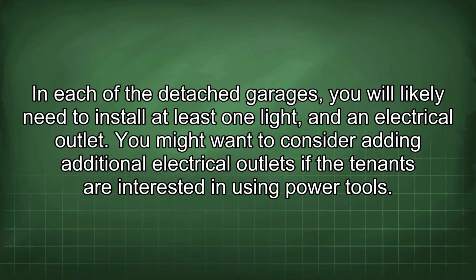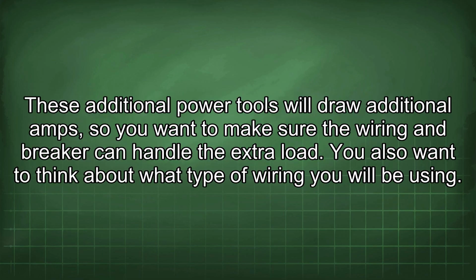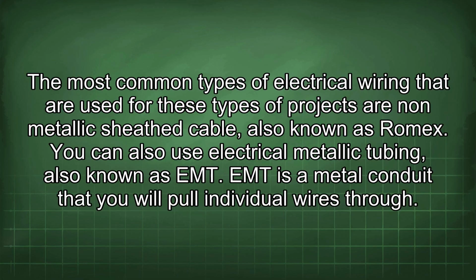In each of the detached garages, you will likely need to install at least one light and an electrical outlet. You might want to consider adding additional electrical outlets if the tenants are interested in using power tools. These additional power tools will draw additional amps, so you want to make sure the wiring and breaker can handle the extra load. You also want to think about what type of wiring you will be using. The most common types of electrical wiring that are used for these types of projects are non-metallic sheath cable, also known as Romex. You can also use electrical metallic tubing, also known as EMT.